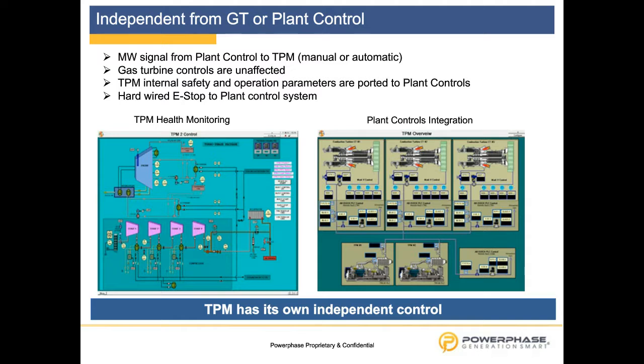For example, if the pressure in the compressor discharge casing is going to be low for whatever reason, or if the temperature is not matching, or if your gas turbine trips, then we are automatically shutting the valve and interjecting immediately, so that no dry air is injected into the existing operations of the gas turbine and harming the compressor.